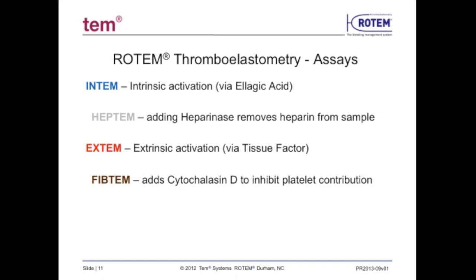Heptem is also used to confirm that a defect demonstrated in the Intem test is due to heparin anticoagulation and not a factor deficiency. The FibTem assay is a modification of Extem — the addition of cytochalasin D inhibits platelet contribution to clot formation, so the resulting amplitude only reflects the quality of the clot due to the fibrin contribution. The test directly measures fibrin activity and can provide an indirect measurement of fibrinogen availability.